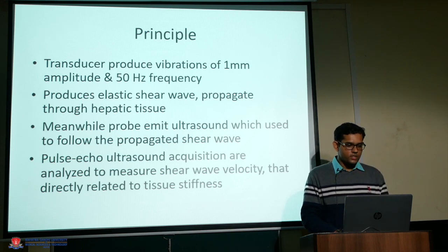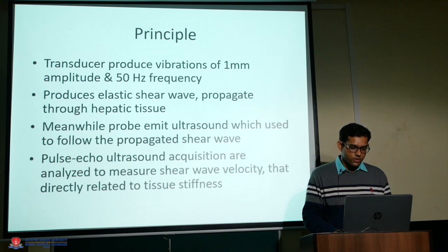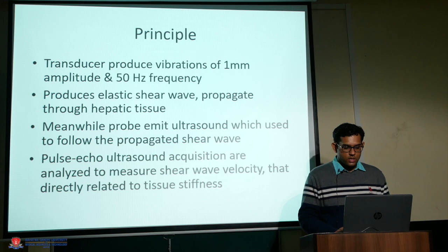Meanwhile, the probe emits ultrasound which is used to follow the propagated shear wave. Now, pulse-echo ultrasound acquisitions are analyzed to measure shear wave velocity, which directly relates to tissue stiffness. Every pulse that is given is analyzed further.